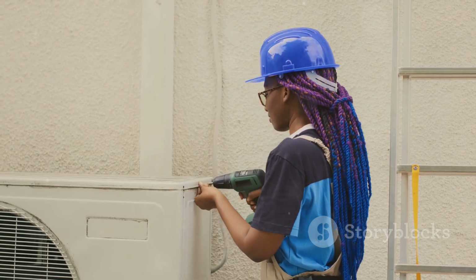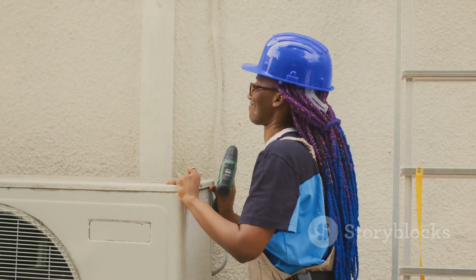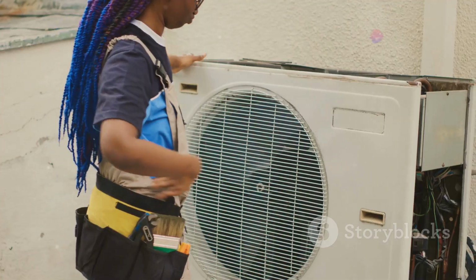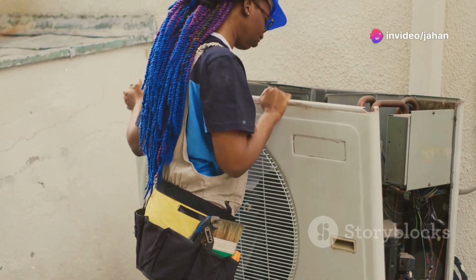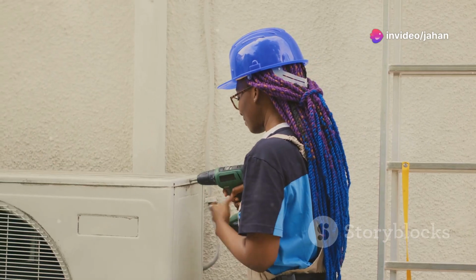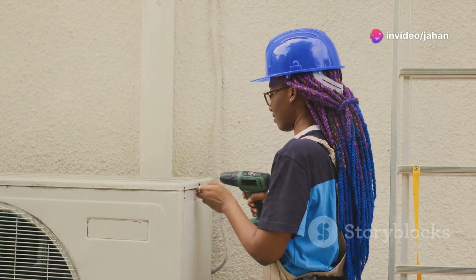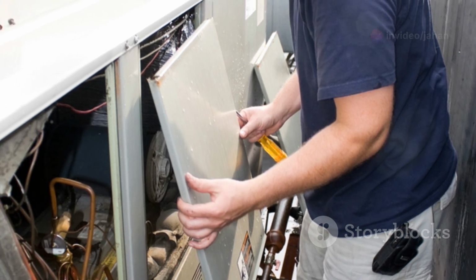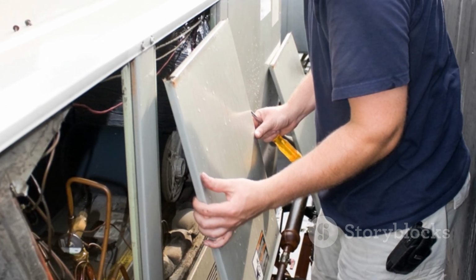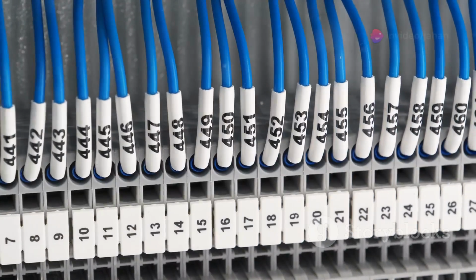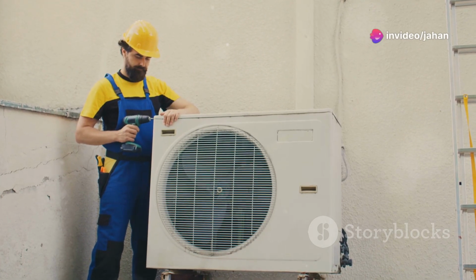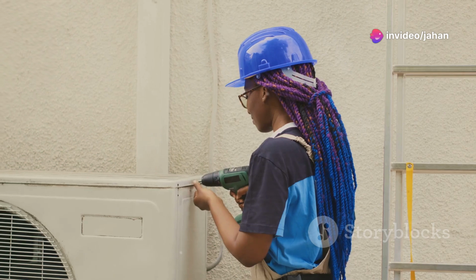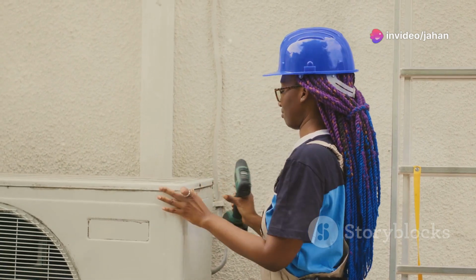Section 6. Disconnecting the old compressor wires and lines. Once the refrigerant is recovered, you can disconnect the old compressor. Start by disconnecting the electrical wires. Take a picture of the wiring before disconnecting. This will help you during reinstallation. Label each wire with masking tape and a marker. This ensures you reconnect them correctly later. Disconnect the refrigerant lines carefully, using wrenches to loosen the fittings.